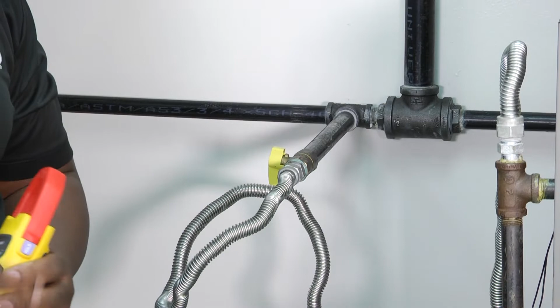Now there are a bunch of components and parts within our system that we need to check. But remember, this was a heating tune-up, a heating clean and check. So vacuum out the cabinet, make sure everything is clean with no dirt and debris. You want it to look better than it did when you got there. So if the homeowner goes in the attic or closet and opens the unit, they should see at least a shiny, clean piece of equipment. We want to make sure we clear out any cobwebs or anything that may have collected inside.